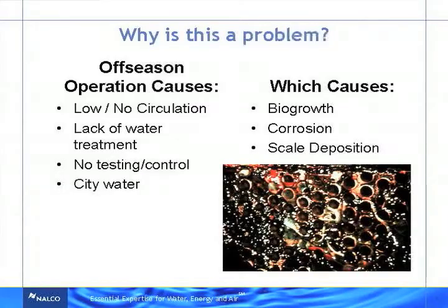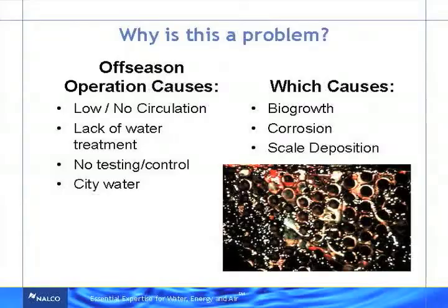So first of all, why is it an issue? Why do we even care about it? What happens during the off-season is you'll get low or no circulation. If you're just shutting your system down and waiting for that random 60-degree day we might get, you're just going to have your system sitting there, or maybe it kicks on for a couple hours a day depending on need. So that would be low or no circulation. The other thing you're going to see is a lack of water treatment. Without circulation, without makeup water, a lot of times you won't be able to inject your chemistry, control your chemistry, use your controllers the same way. If it's not flowing through that rack, it's not measuring what you want to do.